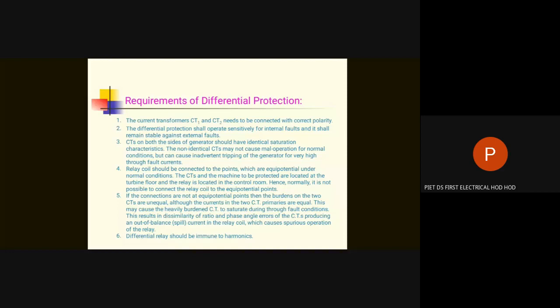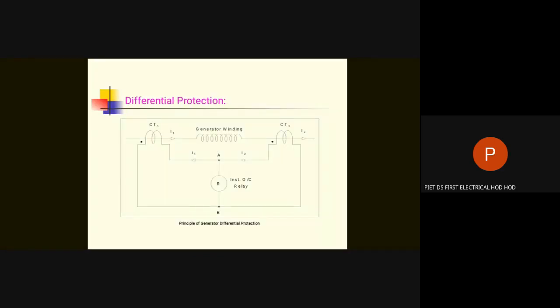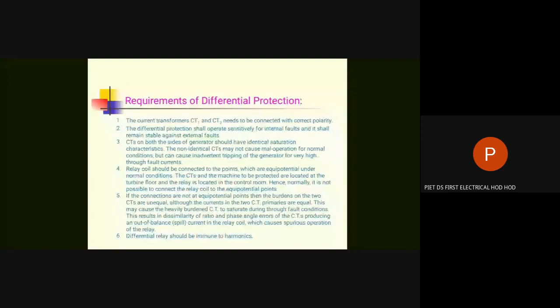In the earlier slide, I had shown CT1 and CT2. CT1 on the neutral side, shall I take the earlier slide? The CT1 in front of you. CT1 is the CT on the neutral side, and then CT2. Both these CTs have to be perfectly identical with reference to their saturation characteristic. Two different CTs to be exactly identical is never possible.